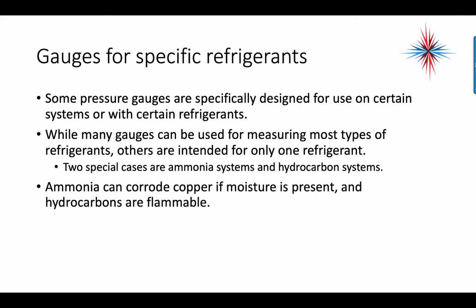There are some pressure gauges designed specifically for use on certain systems or with certain refrigerants. While many gauges can be used for measuring most types of refrigerants, others are intended for only one refrigerant. Two special cases here are ammonia systems and hydrocarbon systems. Ammonia can corrode copper if moisture is present, and hydrocarbons are flammable. Hydrocarbons would be like a propane system.